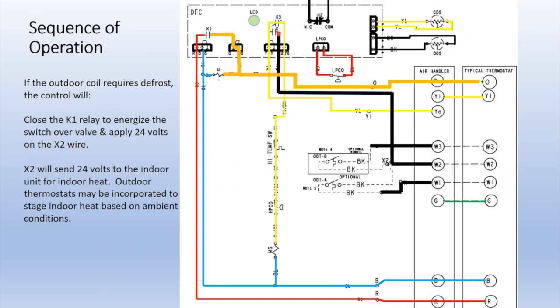It's also the same K1 relay puts 24 volts out X2, which is going to go to your W's on your indoor unit. This is going to run your electric heat or your gas heat, which just tempers the air so that cold air isn't coming out of your ducting during a defrost. Your outdoor fan is also going to turn off because you're warming up that outdoor coil and you don't want to be fighting cold air going across the coil.